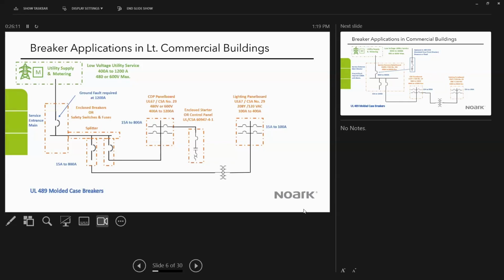And those larger breakers then would feed a panel board under UL 67, which again would have molded case breakers inside it. And then moving on to the right, then you would get successively down into both lower voltage and lower ampacity breakers, coming right to the very end to the lighting panel, which would typically be feeding both lighting circuits and receptacles and things like that at 120 volts. Okay, so that's kind of the structure of a light commercial building.